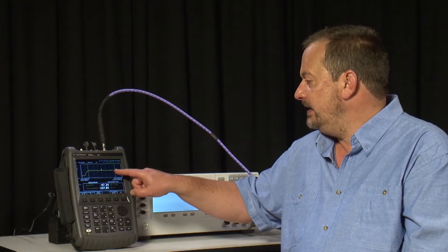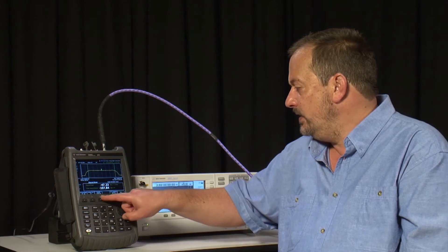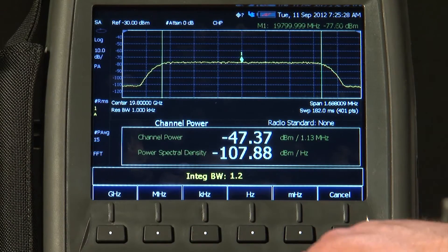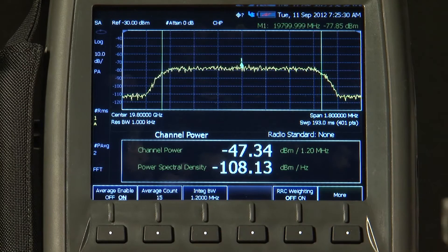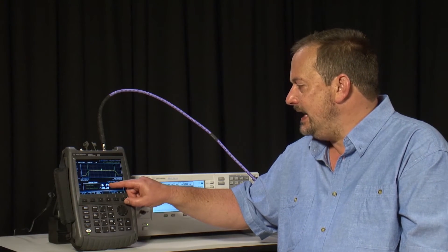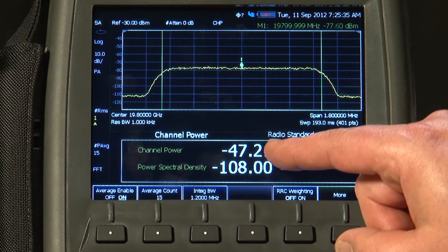Now I know the bandwidth of this signal is roughly 1.2 MHz, so I will just set the integration bandwidth to 1.2 MHz.